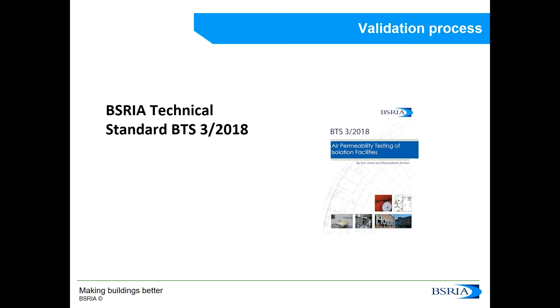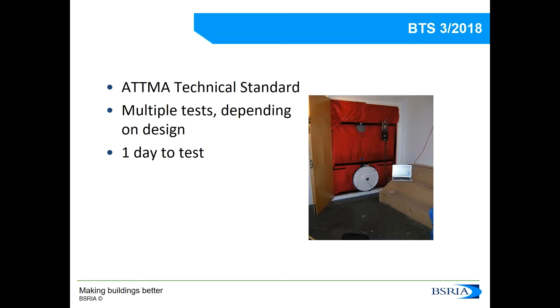Air tightness is a way to measure what the air leakage in a room is. For this purpose, BSRIA has published a technical standard, BTS3 2018, which is free to download from the BSRIA webpage and explains how to do an air tightness test in an isolation suite. This test is based on the ATTMA technical standard, so an engineer who knows how to do an air tightness test can carry out these tests very easily — instead of testing a building or house, we carry them out in an isolation suite. A series of tests are proposed depending on room design, and they should only take one day.